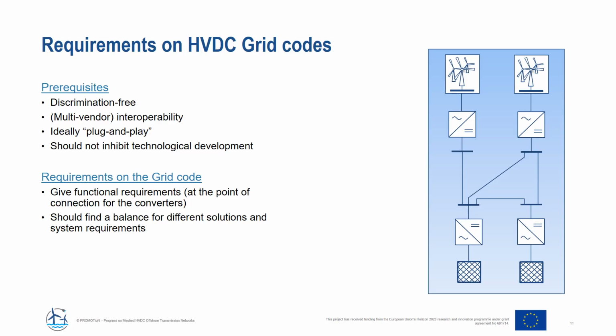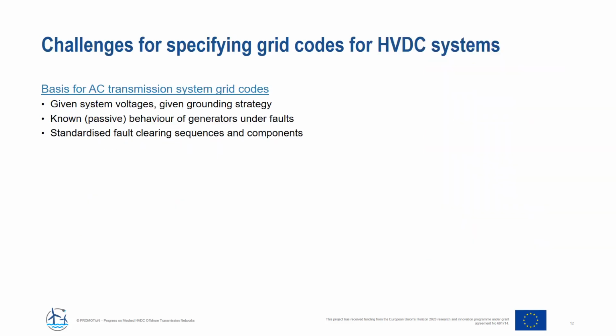When trying to specify corresponding HVDC grid codes at the DC point of connection, we run into several challenges. So first, let's have a look. What was the basis for AC transmission system grid codes? In general, that was a given system voltage and a given grounding strategy. It was the known passive behavior of generators under faults, allowing the system operators to define corresponding AC fault ride-through profiles, for example. And there are standardized fault clearing sequences and components.